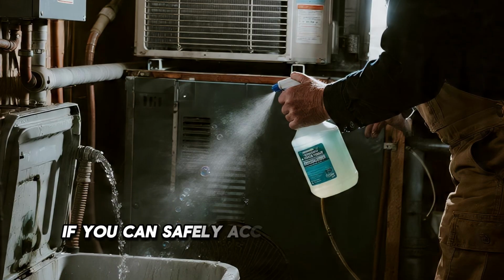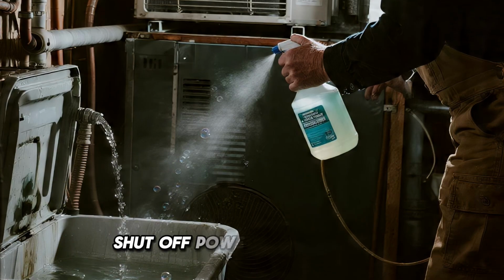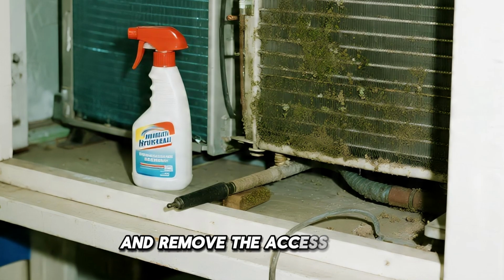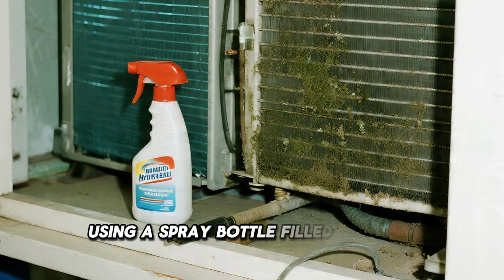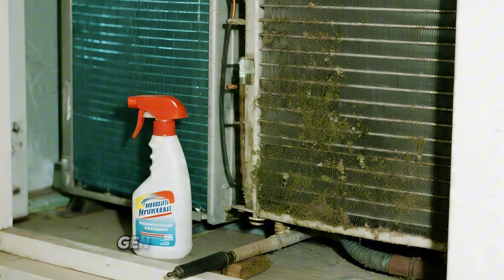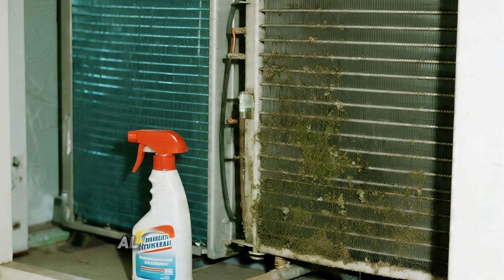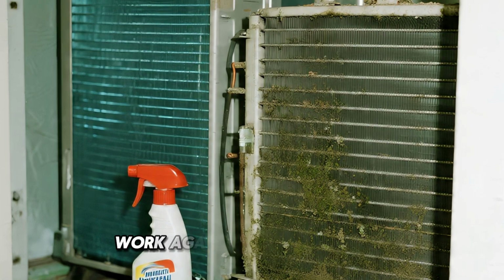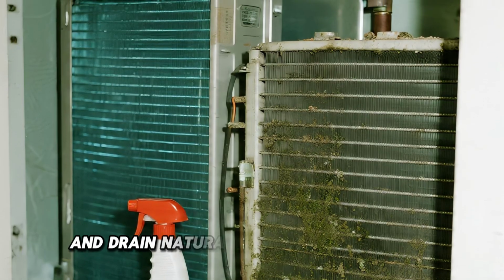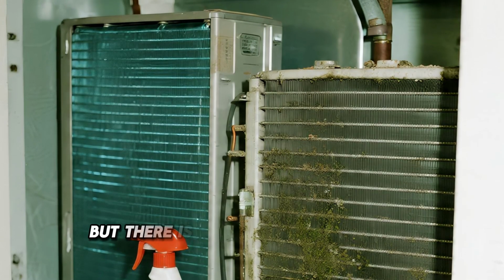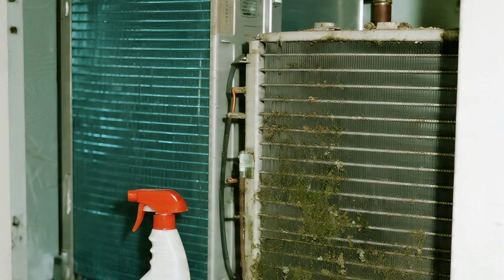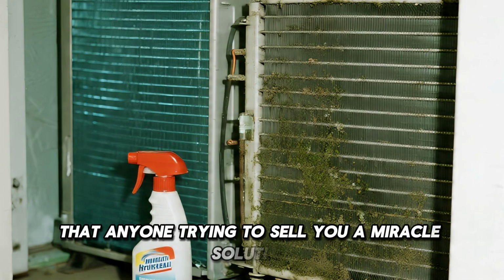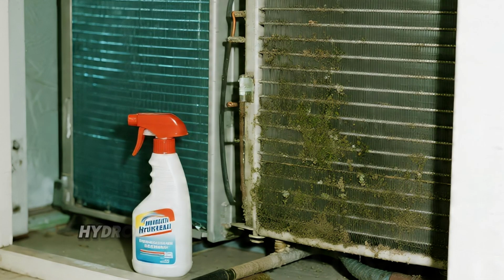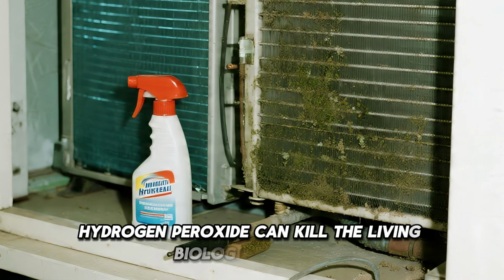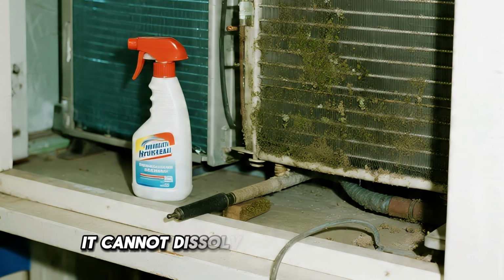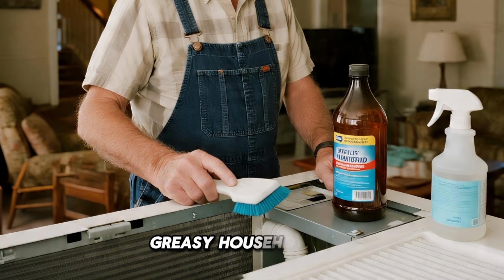If you can safely access the evaporator coil, shut off power at the breaker, and remove the access panel. Using a spray bottle filled with 3% hydrogen peroxide, gently mist the aluminum fins. Allow the peroxide to bubble, work against the living layer, and drain naturally into the pan below. But there is an important technical limitation here that anyone trying to sell you a miracle solution probably won't mention. Hydrogen peroxide can kill the living biological layer. It cannot dissolve years of baked-on, greasy household dirt.